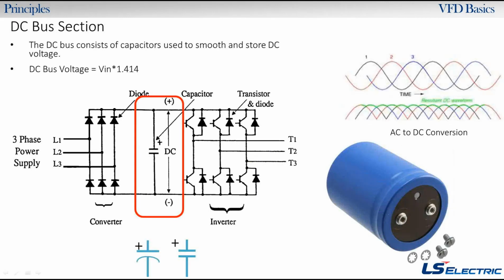So moving along, so now we have AC over to DC, but now we got to store that DC somewhere. So what we do is we store that DC on DC bus capacitors. Even though this diagram here is just showing one, this is a very simplified diagram, okay? Most of the time, you're going to have 2, 4, 6, 8, 10, many capacitors in there. You're not going to have just one capacitor. What capacitors are used for is smoothing out and storing that DC bus voltage, okay? So we rectify the AC to the DC voltage, and then now we need somewhere to store it.